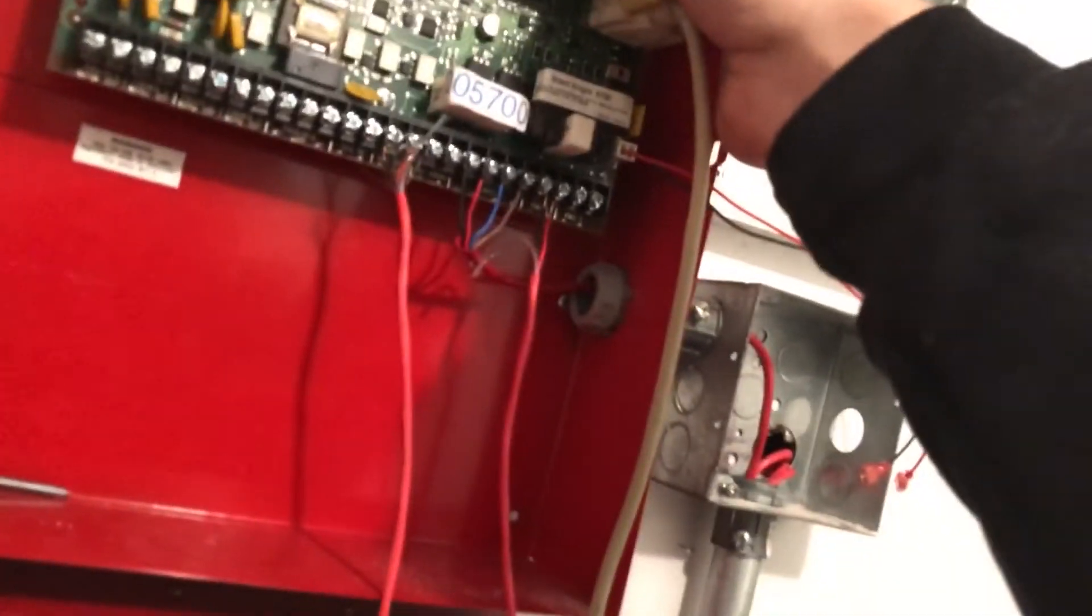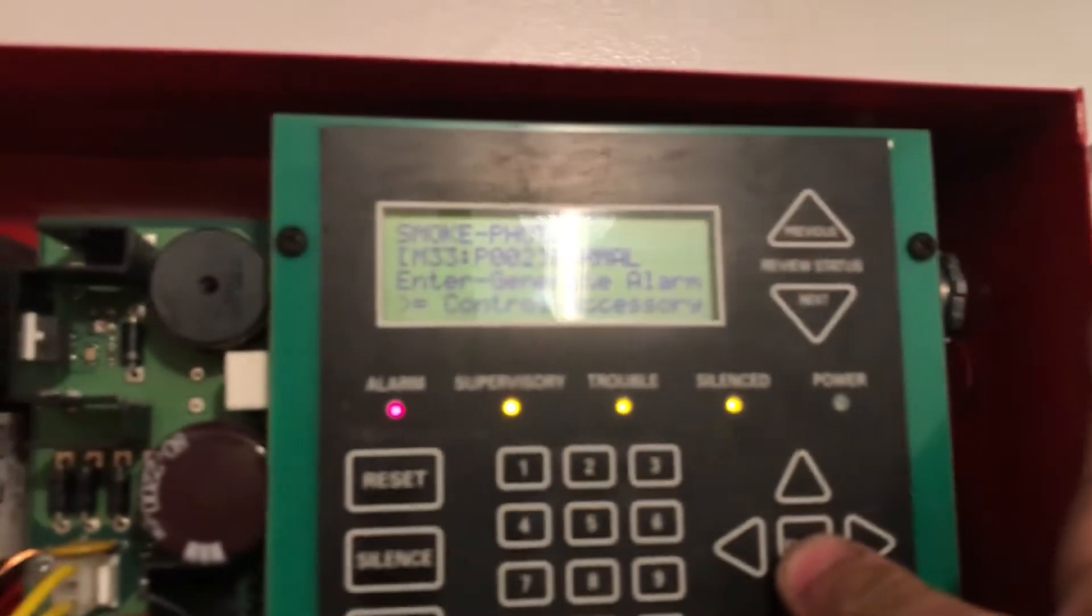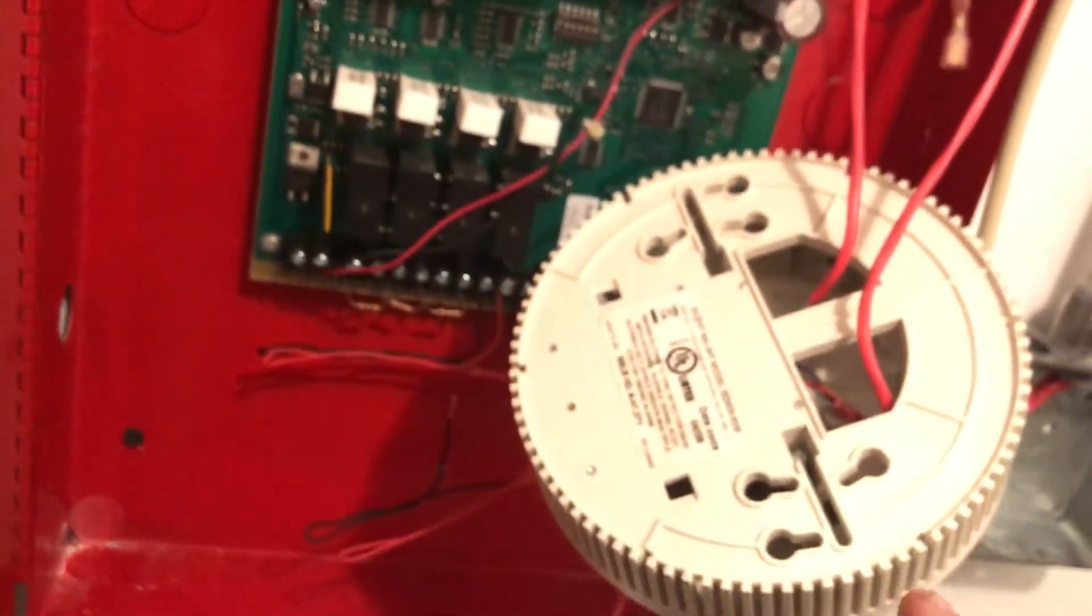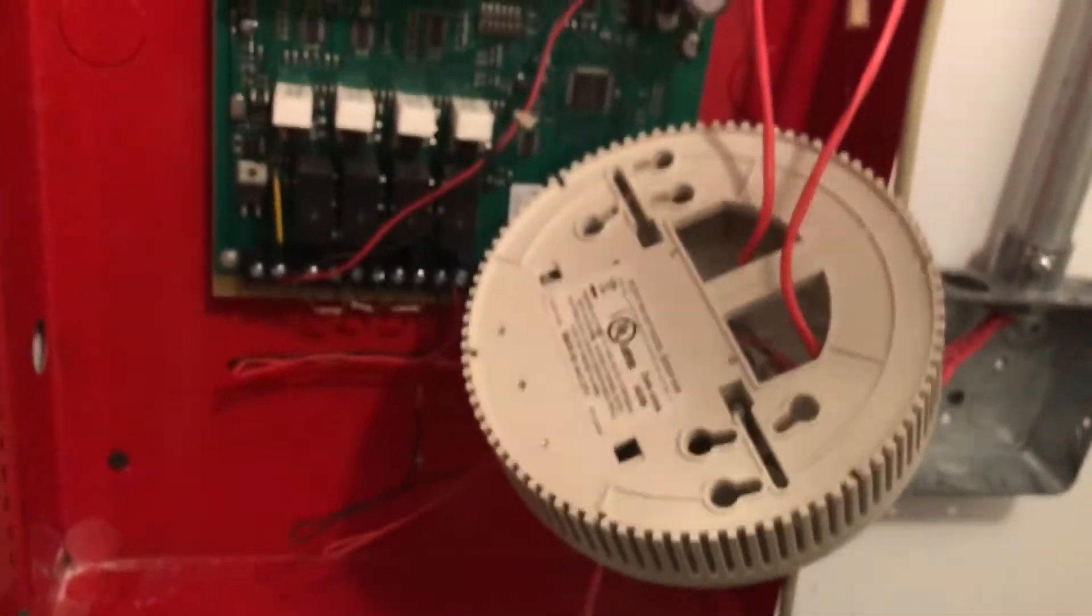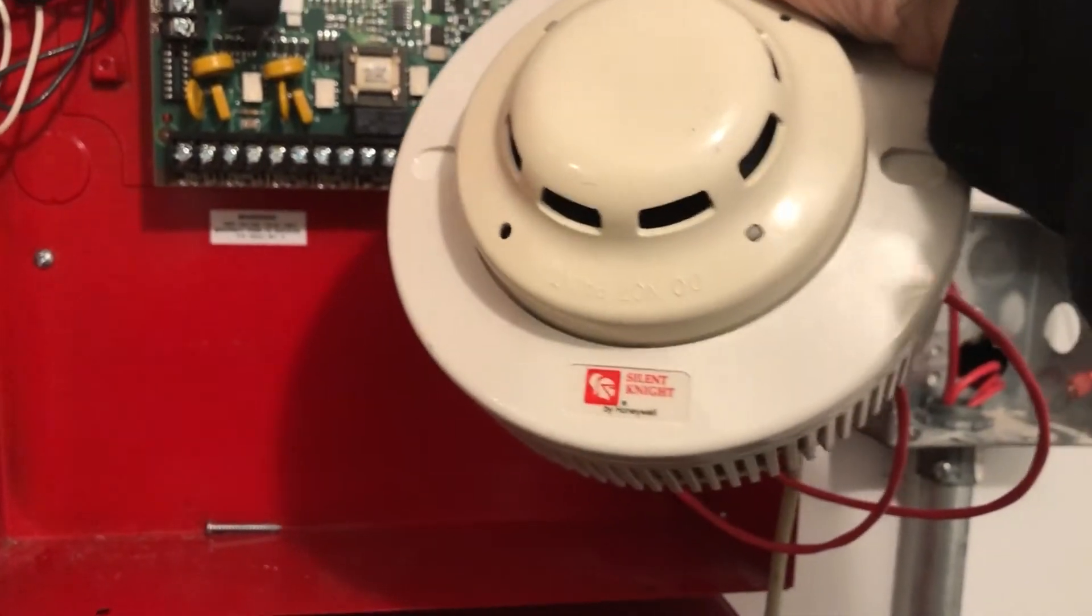And now, last but not least, we're going to try the only device which is connected, which is our photo smoke detector, which will make this smoke detector sounder base do code three. Three, and you can actually see the lights go on. Three, two, one.